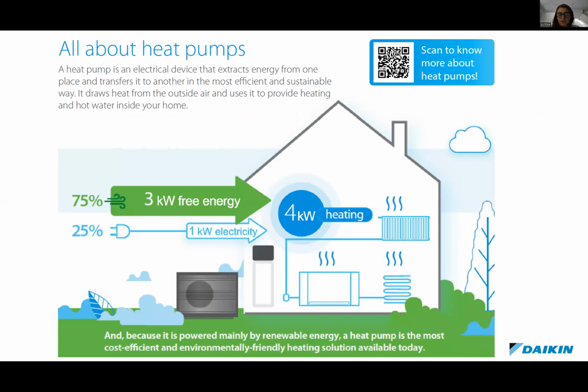So just in terms of the efficiency, for anyone that's new to looking at how this technology works, it's a renewable energy source. It takes its energy from the air. And the term that we use for efficiency with heat pumps is COP, coefficient of performance. That relates to the amount of energy that we use to run the heat pump versus the amount of energy that we get from the heat pump. So this diagram represents that for one unit of electricity, we get 3 units of energy free from the air. And that gives us a total of 4 units of energy for heating our house. So that's basically a COP of 4.